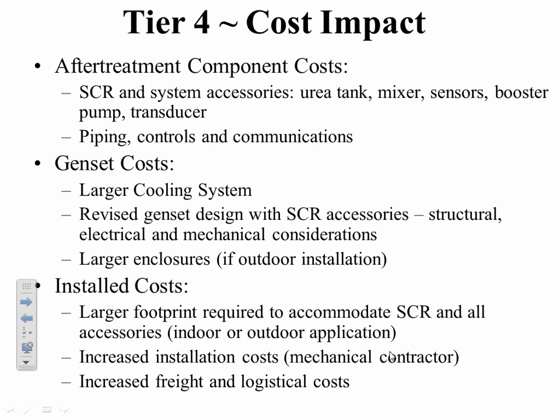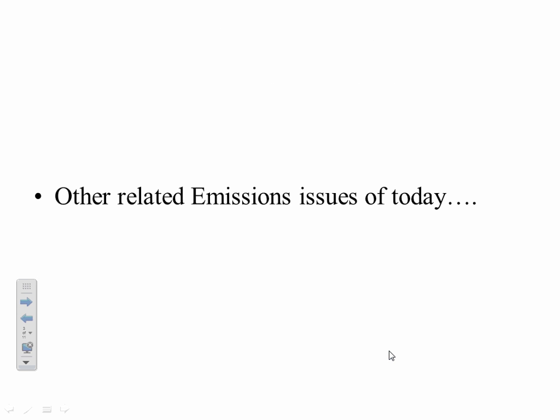After-treatment component costs, that's a little summary of what we'll need for NOx. Genset costs are the other thing. We're going to need a larger cooling system, a revised genset design with the accessories, the SCR. We also have to look at the back pressure. What are these components going to do to back pressure on the engine? So it's probably going to be larger piping on the outlets and so on. No derating of the engine? Possibly some, but that all has to be considered now in doing a generator sizing. Larger enclosures. Now we've got a bunch more stuff. If we're going to have an outside unit, now we have to fit the SCRs and all those components in the box as well. So a lot of related things are going to drive the cost up.